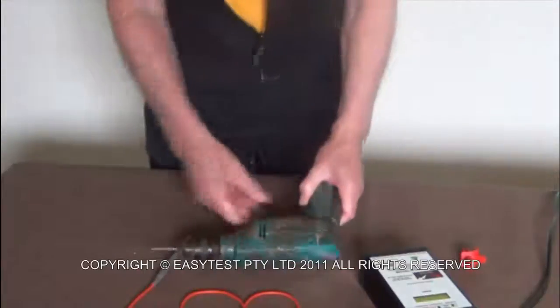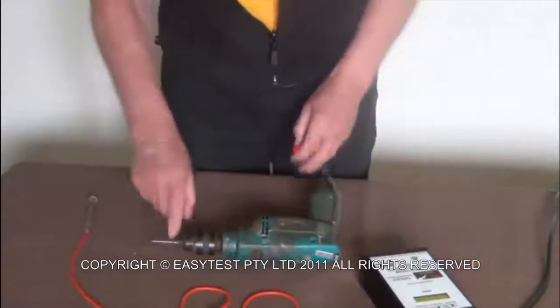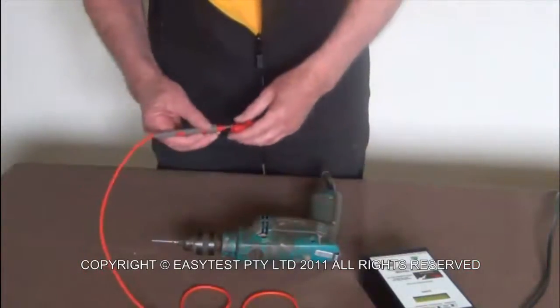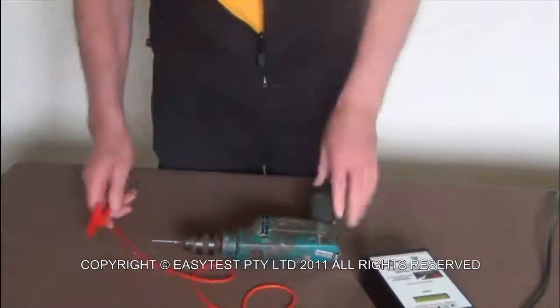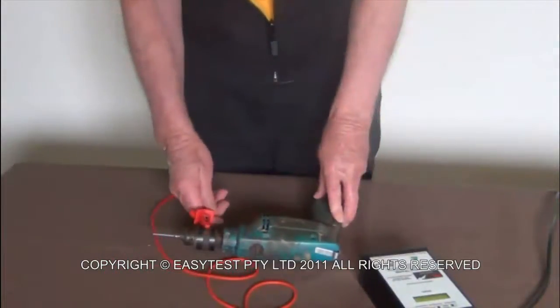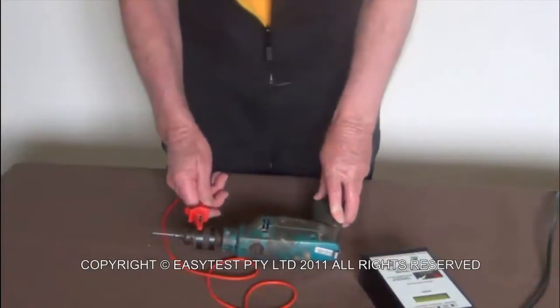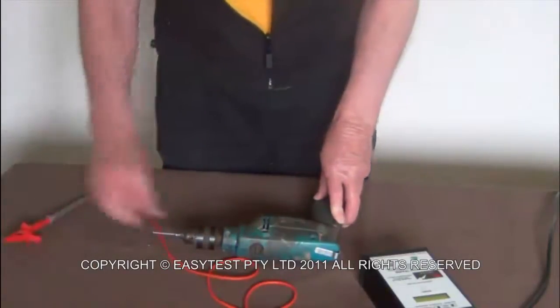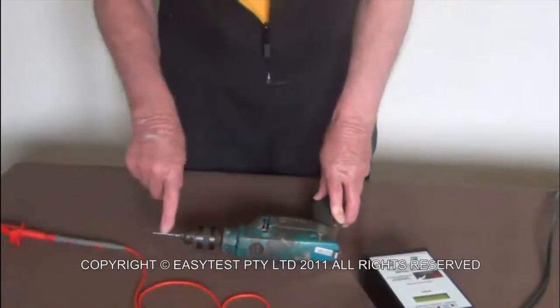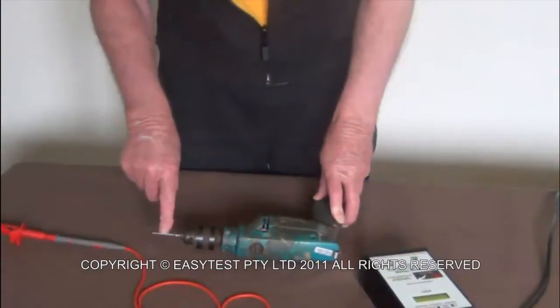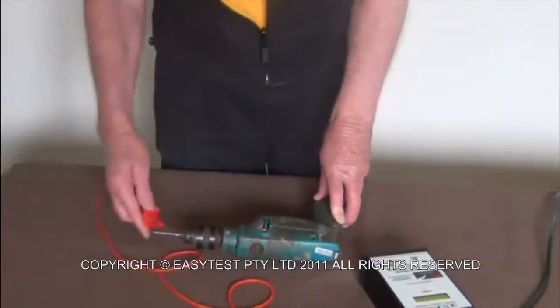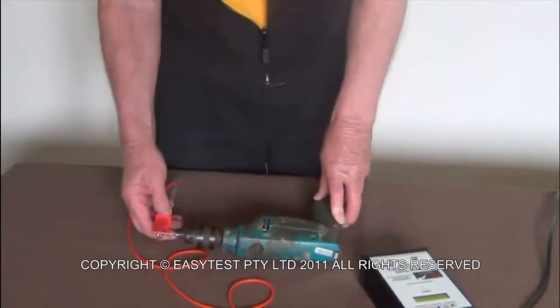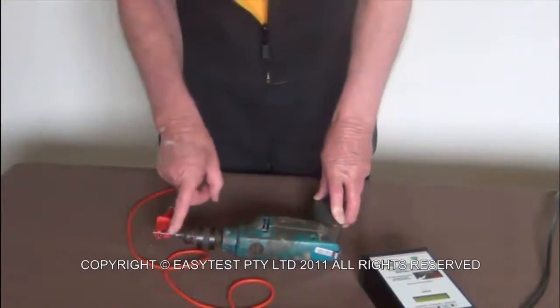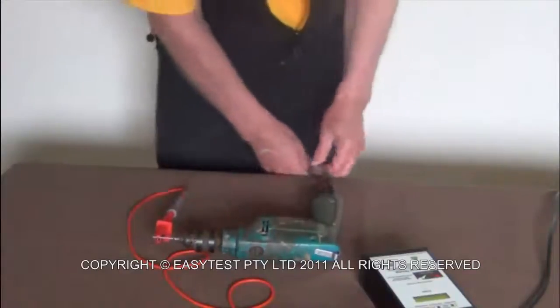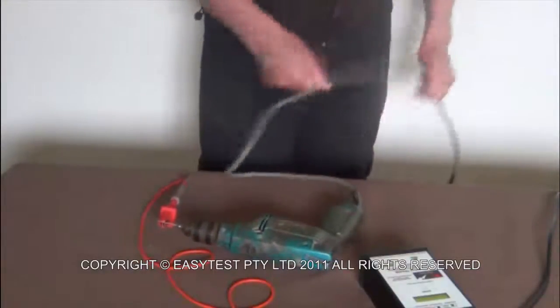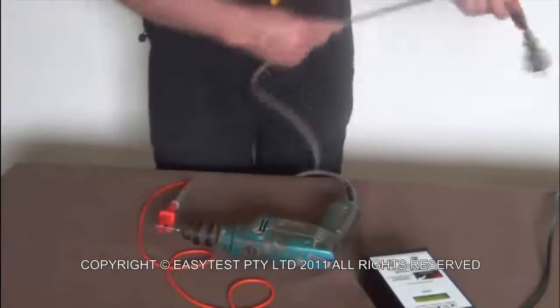Here's a drill. Similar problem, it has a rotating part, but the standard says you have to check for earth leakage to all exposed metal. So what I like to do with this, I get a small drill, this one's about 3mm, 1/8, whatever you like to call it, and I attach my probe to that. Now that will spin quite safely inside the clamp.